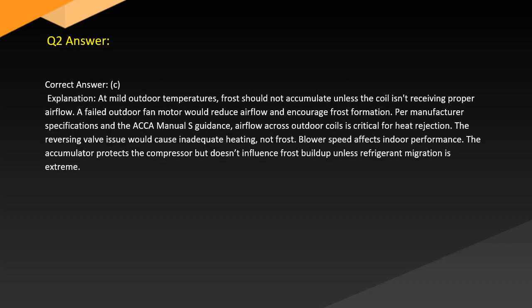Answer. Correct answer: C. Explanation. At mild outdoor temperatures, frost should not accumulate unless the coil isn't receiving proper airflow. A failed outdoor fan motor would reduce airflow and encourage frost formation. Per manufacturer specifications and the ACCA Manual S guidance, airflow across outdoor coils is critical for heat rejection. The reversing valve issue would cause inadequate heating, not frost. Blower speed affects indoor performance. Accumulator protects the compressor but doesn't influence frost buildup unless refrigerant migration is extreme.